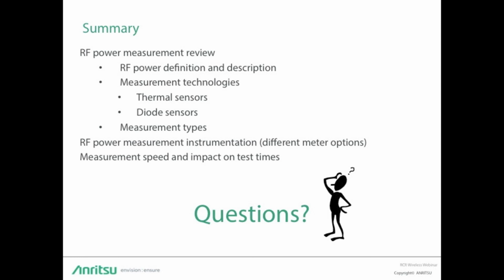I think we have time for a couple more questions. You mentioned the need to watch out for the fine print. Can you give a particular example of areas in which we need to be careful? The key with that one is that when you're comparing across sensors, you really want to make sure that you're comparing apples to apples. Measurement uncertainty is a good example of that. One data sheet for a sensor might include things like the zero set and drift, and one might not. So as you are looking through the data sheets, look through the footnotes and make sure that you understand specifically what's included in each of the measurements, how long it's covering, the full power range, those kinds of things, so that you're comparing sensors correctly.